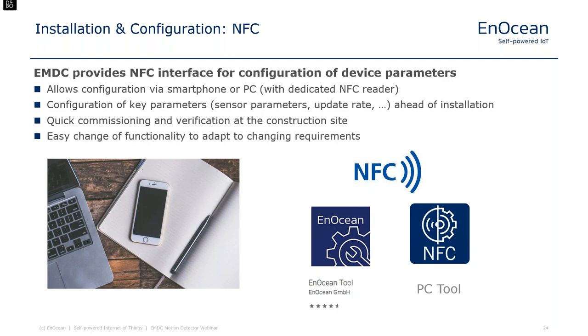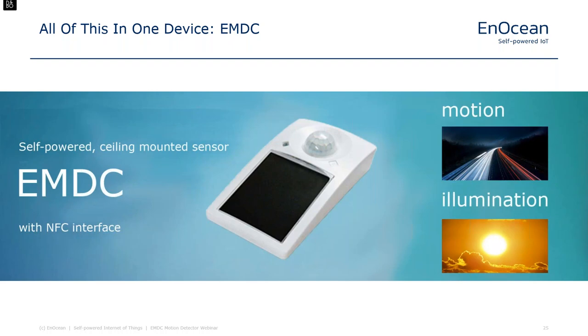You also need to be able to set up the device according to your needs — telling the receiver the sensor ID, type and security key. This configuration process is a key cost-saving opportunity, as time spent configuring devices on a construction site directly impacts revenue. Therefore in our latest generation products we use an NFC interface that can be easily configured using a dedicated smartphone application or a PC tool. This allows installers to use a smartphone on-site, and partners to use a PC tool during manufacturing. All functionality — motion detection, illumination measurement and NFC configuration — is integrated in EMDC, a self-powered ceiling-mount device.